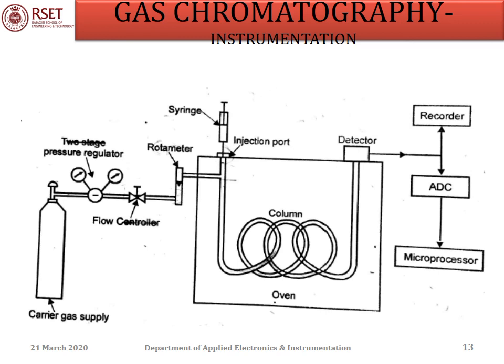The basic parts of gas chromatography are: carrier gas supply along with pressure regulator and flow regulator for constant flow of carrier gas; sample injection system for introduction of sample vapors into the flowing gas stream; chromatographic column with an appropriate length of stationary phase; thermal compartment or thermostat for maintenance of the column at appropriate temperature; detection system for detection of sample components as they elute from the column; and a microprocessor or recorder to provide a readable signal proportional to the amount of each component present in the analyte.